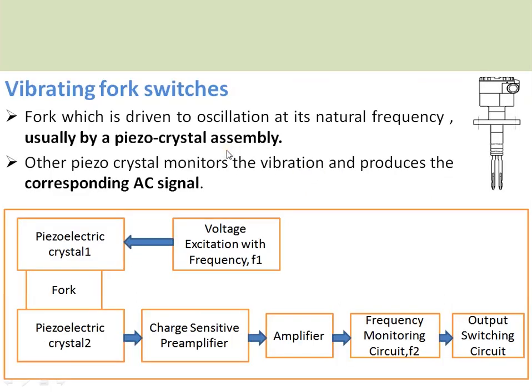This vibrating type level switch consists of two piezoelectric crystals. The property of the piezoelectric crystal is: if you give a voltage excitation to it, it will vibrate; and conversely, if you give a vibration to this piezoelectric crystal, it generates an electrical signal. As shown in the block diagram, one piezoelectric crystal gives vibration to the fork, while another piezoelectric crystal monitors these vibrations — converting electrical to mechanical and mechanical to electrical signals respectively.